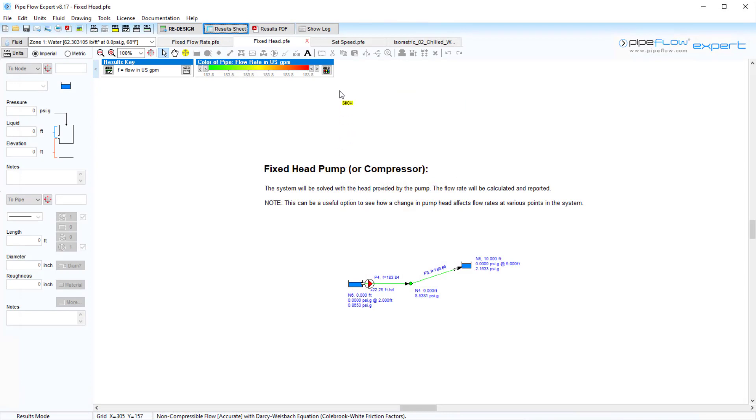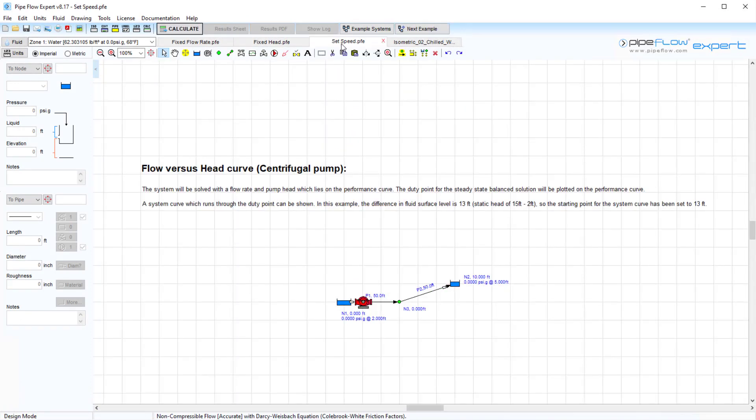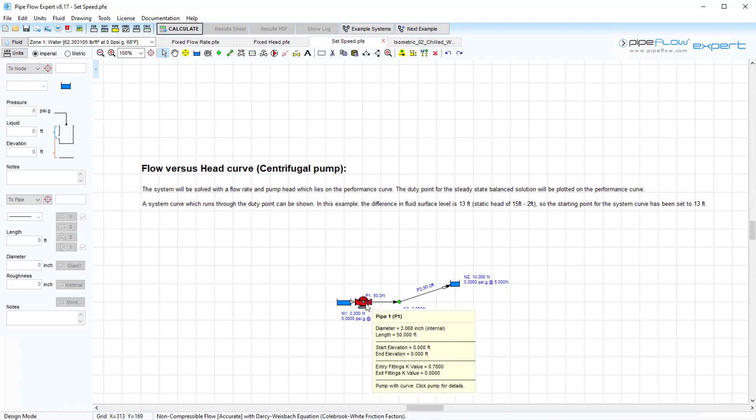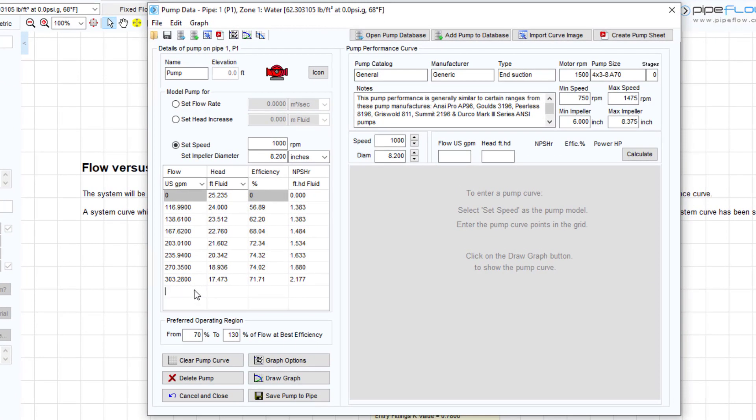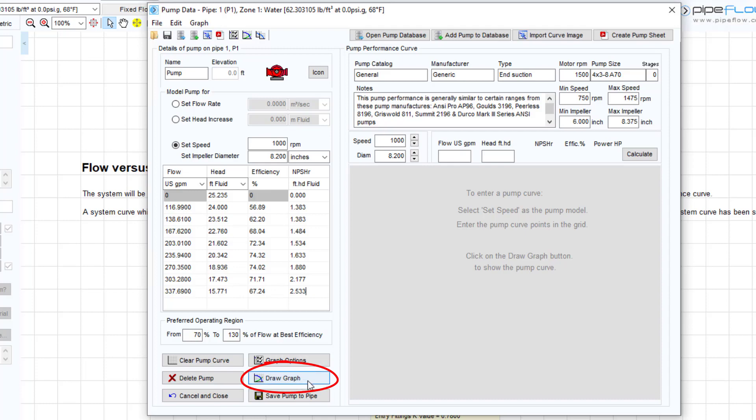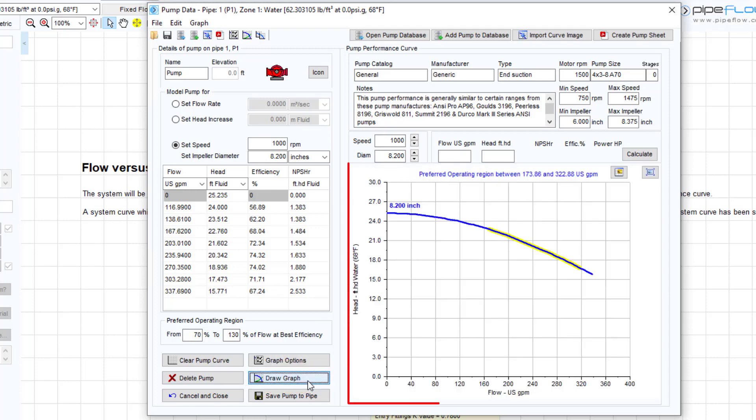Often a pump manufacturer will provide you with a range of flow versus head loss data which can be entered into the pump data table when the set speed option is selected. We will finish entering the data points for this particular pump and click draw a graph. The operating curve is then drawn on the pump data screen.